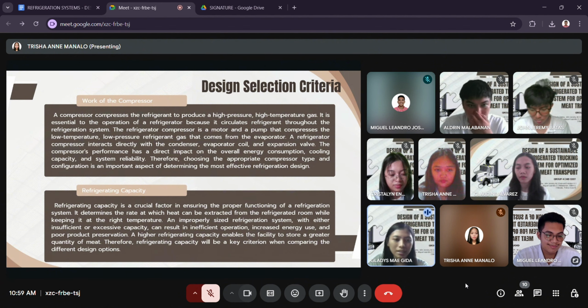Second, refrigerating capacity. It is a crucial factor in ensuring the proper functioning of a refrigeration system. It determines the rate at which heat can be extracted from the refrigerated room while keeping it at the right temperature. An improperly sized refrigeration system, with either insufficient or excessive capacity, can result in inefficient operation, increased energy use, and poor product preservation. A higher refrigerating capacity enables the facility to store a greater quantity of meat. Therefore, refrigerating capacity will be a key criterion when comparing the different design options. Next slide.